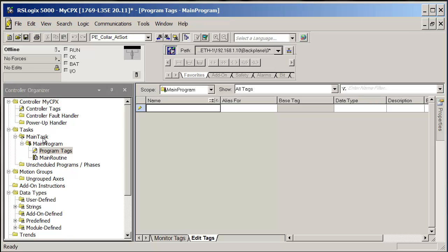The point is, in the Logix engine you can have more than one program, which means that you have to separate the program tags out to the program, because each program has its own data table. Just like if you had 3 MicroLogix processors, they each have their own database. But you could include the I/O in that database because there was only one database.